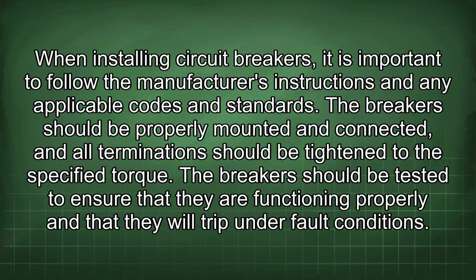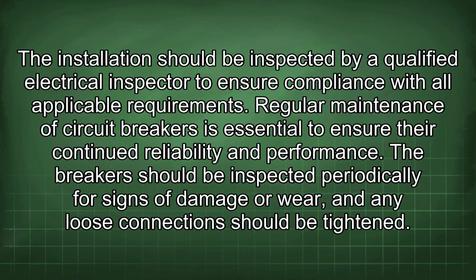When installing circuit breakers, it is important to follow the manufacturer's instructions and any applicable codes and standards. The breaker should be properly mounted and connected, and all terminations should be tightened to the specified torque. The breakers should be tested to ensure that they are functioning properly and that they will trip under fault conditions. The installation should be inspected by a qualified electrical inspector to ensure compliance with all applicable requirements.